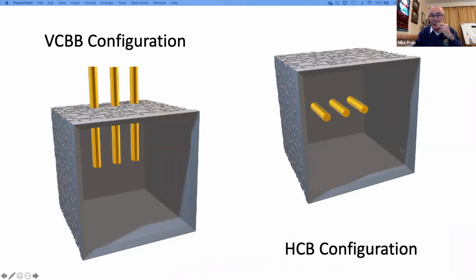And the configuration on the right-hand side is called HCB, which is horizontal conductors within a box. And they're pointing outwards inside a metal enclosure. It's particularly aggressive, this particular configuration, as the plasma from the arc is directed outwards from the ends of the electrodes and directly at the worker. I saw a demonstration of this years before it appeared in the standard. I saw it in IPH laboratories in Berlin, probably about 10 years ago. And it is pretty aggressive to see in the flesh, there's no doubt about that.